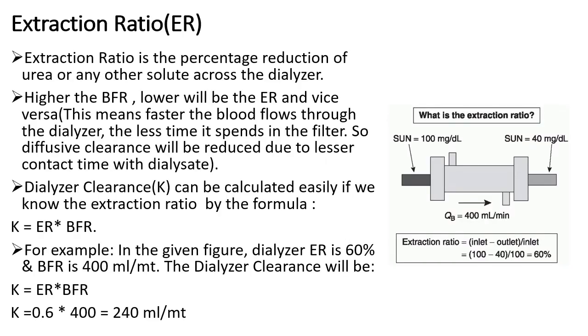The second characteristic is extraction ratio, or simply ER. Extraction ratio is the percentage reduction of urea or any other solute across the dialyzer. Looking at the figure on the right side of the slide, the dialyzer inlet urea concentration is 100 mg/dL and the outlet is 40 mg/dL at a blood flow rate of 400 ml per minute. We can calculate the extraction ratio using the formula: ER = (inlet concentration − outlet concentration) / inlet concentration.